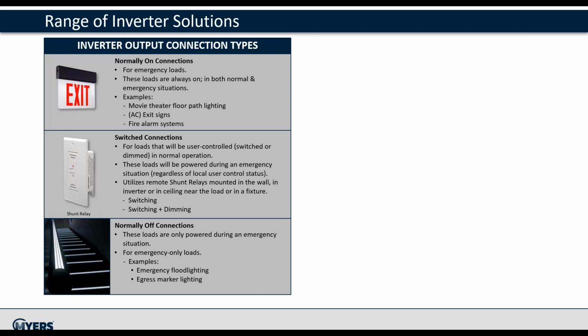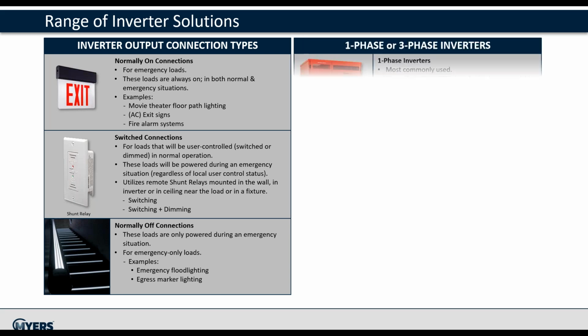Inverter output types include normally on, which are loads that are powered in both non-emergency and emergency situations, such as exit signs. Switched loads are controlled by switches during normal operation and forced on in emergency, such as dusk to dawn lighting and standard room lights. And normally off loads are only powered during emergency operation, such as floodlights or pathway lighting.